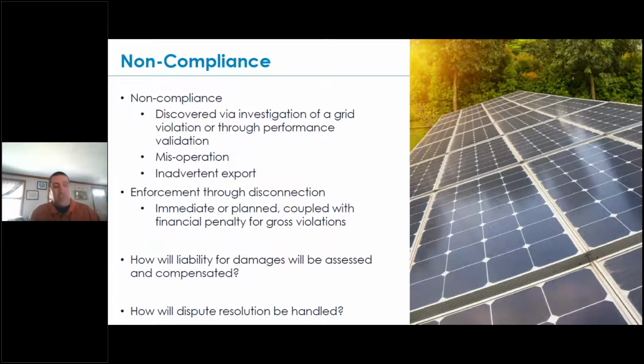So we disconnected that customer, then worked with them to resolve the specific issue. We changed the protection system so they could only operate at about 85% of maximum export, until they could reset their system and controls so the violation wouldn't happen anymore, then we relaxed the protection system so they could go back to 100% output. They were out for a few weeks while we figured out the system, then on their 85% limit for a few months before they got their control system back online.